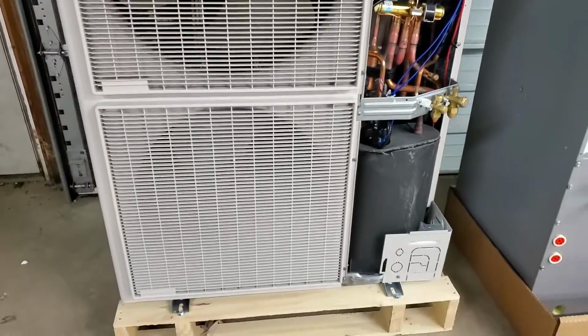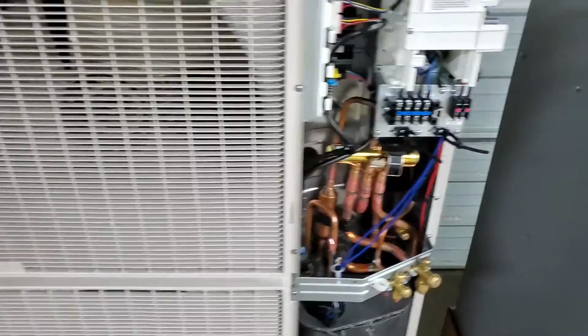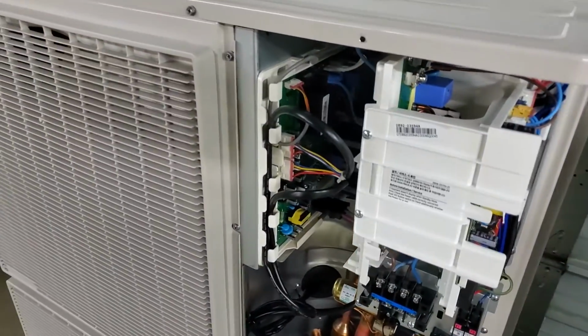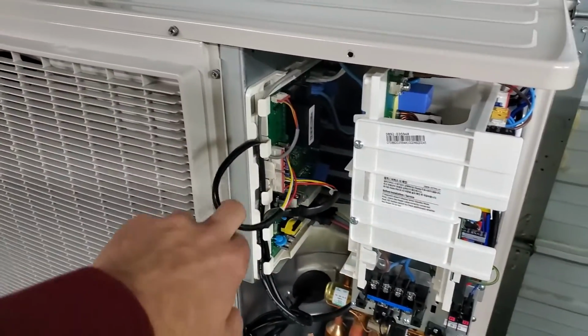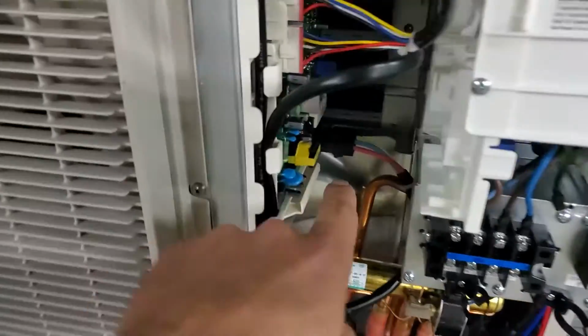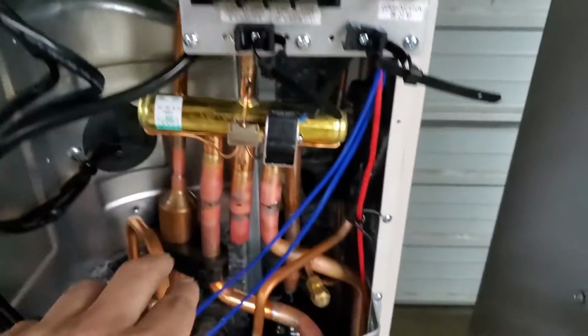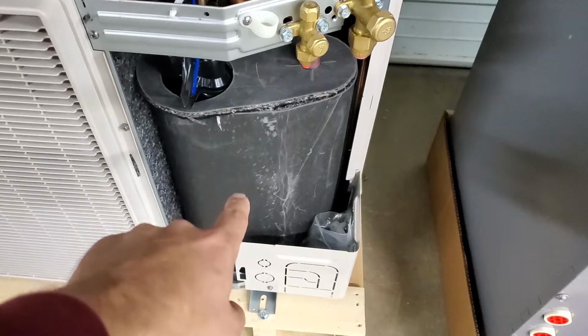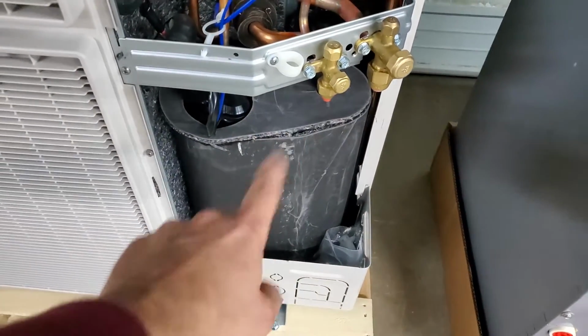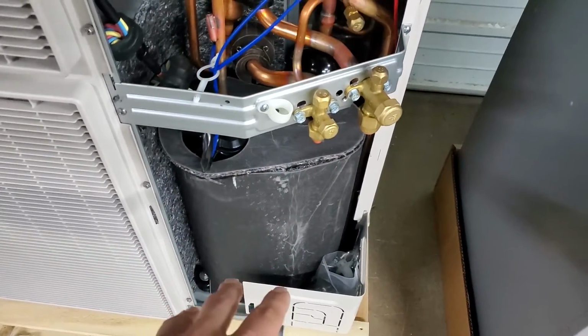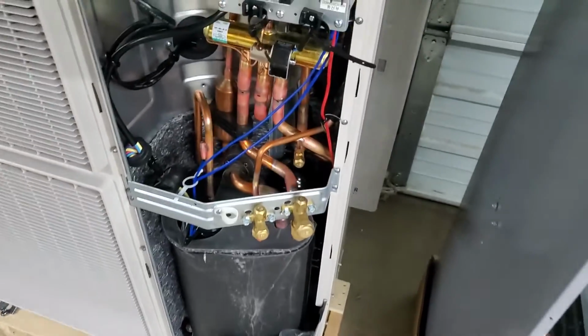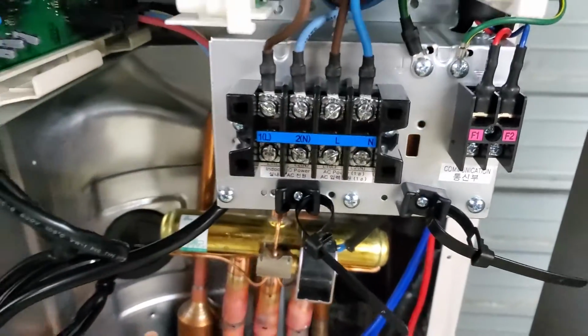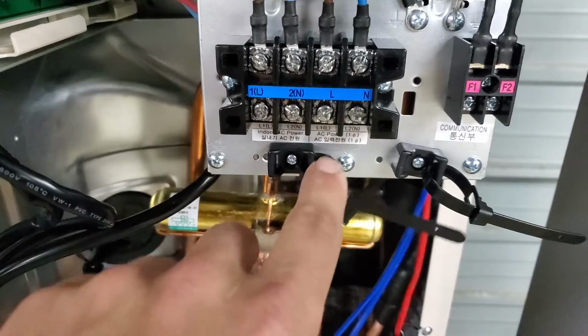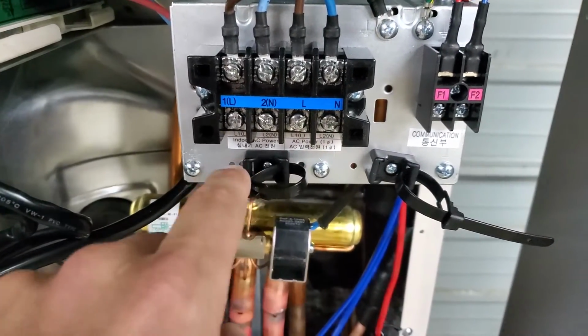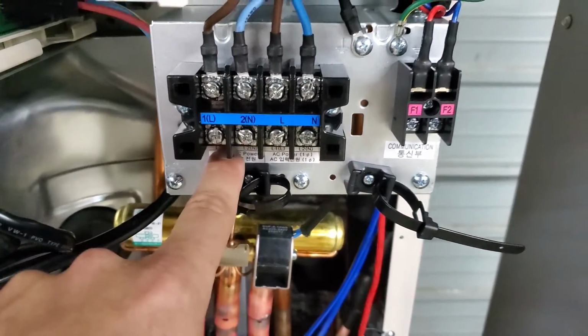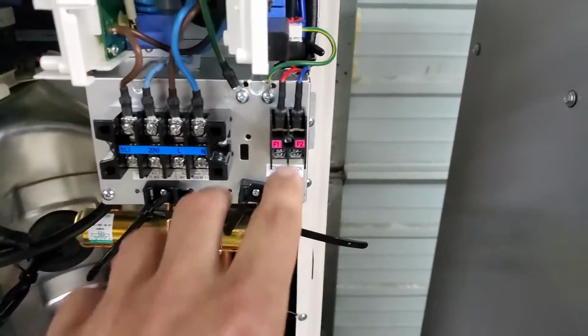This is BLDC, brushless DC fan motors, and they are basically driven by this inverter board. This inverter board also has a 3-wire plug that leads to the twin BLDC inverter-driven rotary compressor. This compressor has the ability to modulate, to change frequency. Then we have our power input. We have our power for our outdoor unit, and then this is the power that leads to the indoor unit. So our outdoor unit powers the indoor.